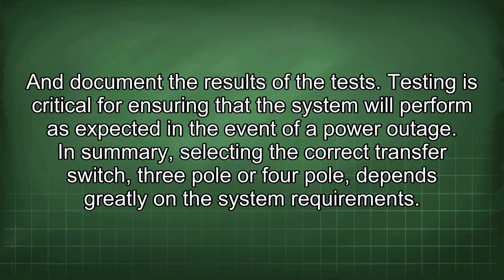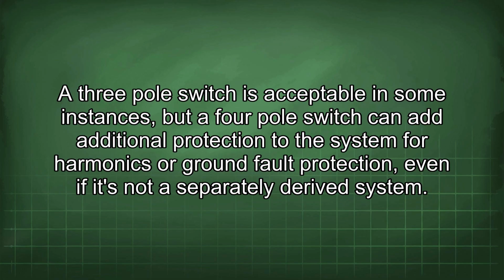In summary, selecting the correct transfer switch, 3-pole or 4-pole, depends greatly on the system requirements. A 3-pole switch is acceptable in some instances, but a 4-pole switch can add additional protection to the system for harmonics or ground fault protection, even if it's not a separately derived system.